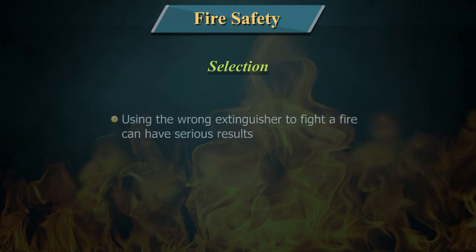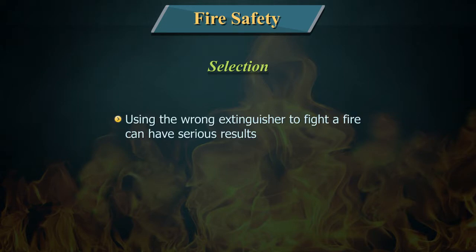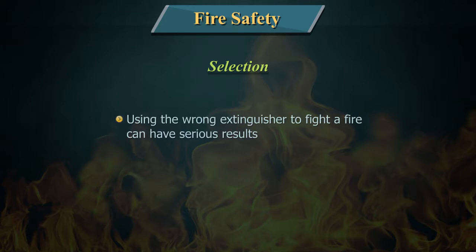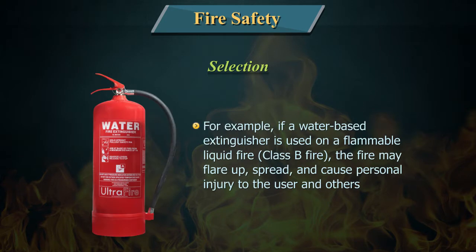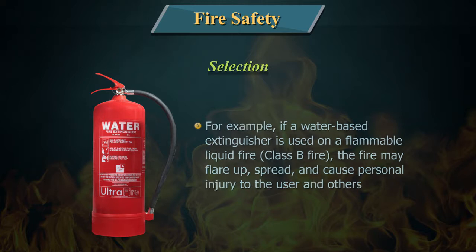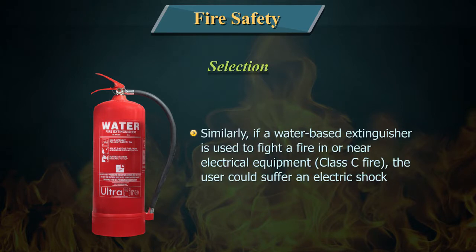Selection: Using the wrong extinguisher to fight a fire can have serious results. For example, if a water-based extinguisher is used on a flammable liquid fire (Class B fire), the fire may flare up, spread, and cause personal injury to the user and others.